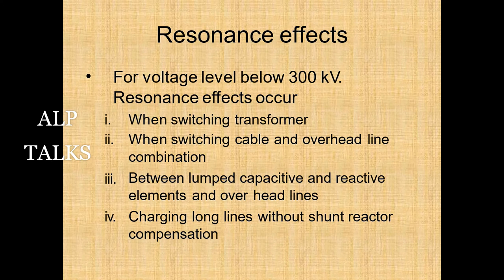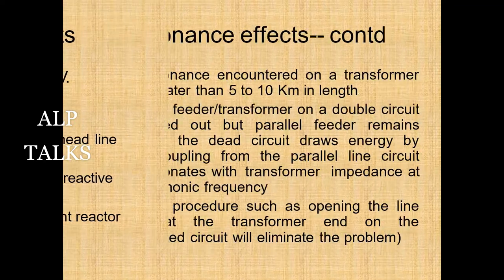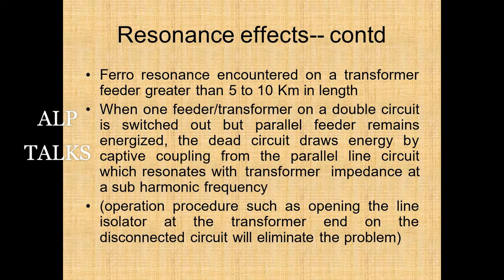Resonance effects below 300 kV occur when switching transformer-cable and overhead line combinations, between lumped capacitance and reactive elements, and when charging long lines without shunt reactor compensation. Ferroresonance is encountered when a transformer with a cable length greater than 5–10 km is involved: when one transformer on a double-circuit is switched out but the parallel feeder remains energized, the dead circuit gains energy by capacitive coupling from the parallel line, which resonates with transformer impedance at sub-harmonic frequencies. Opening the line isolator at the transformer end eliminates this problem.